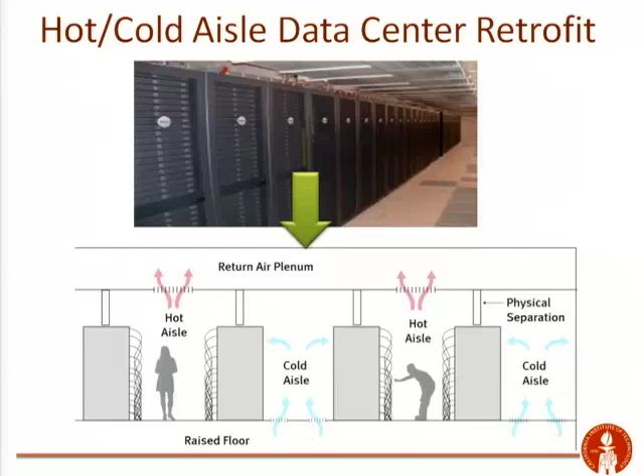We were up at about 250 gallons per minute of chilled water. That's a sort of metric for how much energy we're using in that room to cool that room. We implemented the project of putting up those physical barriers, and our predictive models understood that if we did all those measures, we would be at about 50 gallons per minute from the savings. Well, when we implemented those dividers, we were only at about 150.